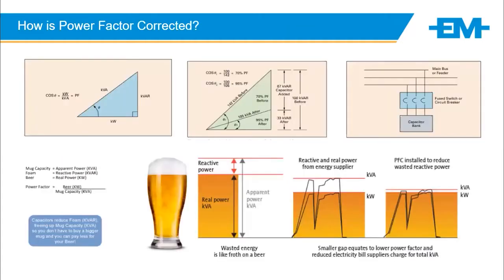So how is power factor corrected? So I referred to COS and PF is kilowatt over kVA. We call this the power triangle. If kVA equals kilowatt, we wouldn't have this COS angle in here. All right. Now we have a little bit of an example. I'm not going to go into the maths here. I had 150 kVA before, and I had a really bad power factor. I introduced a capacitor bank, which reduced the demand at point of injection.